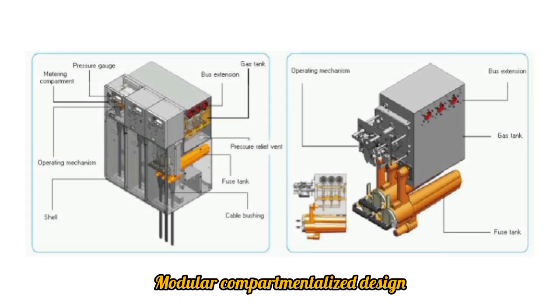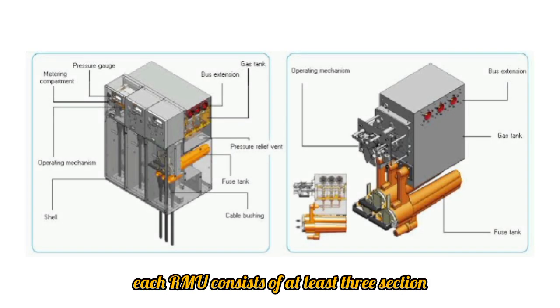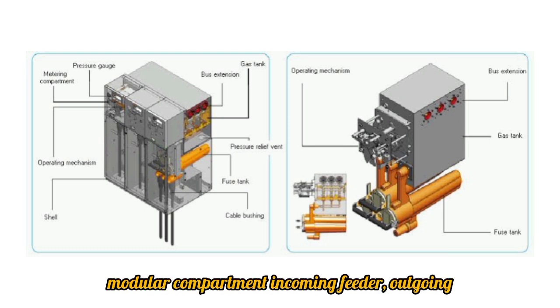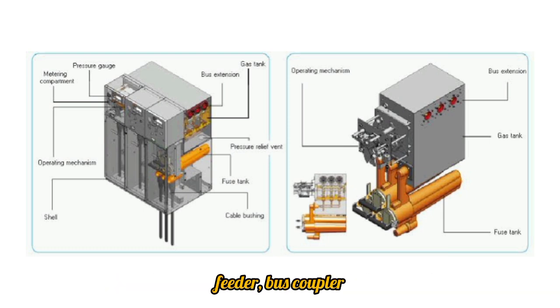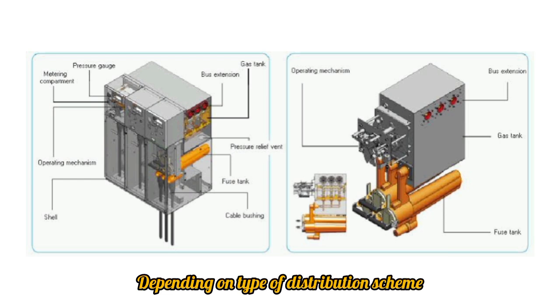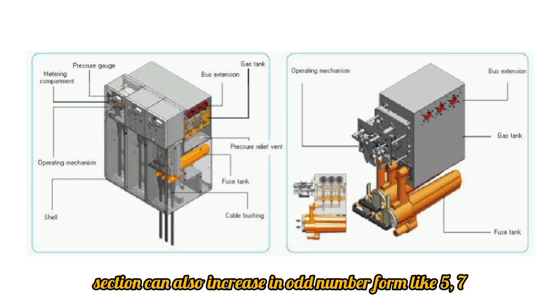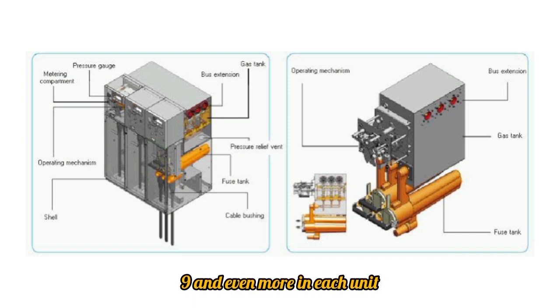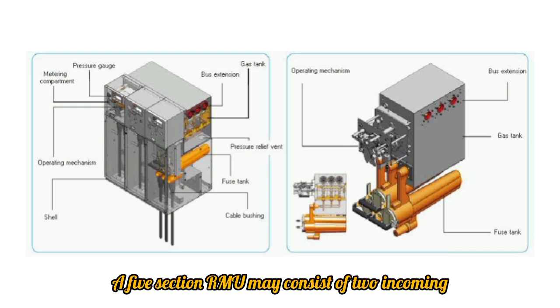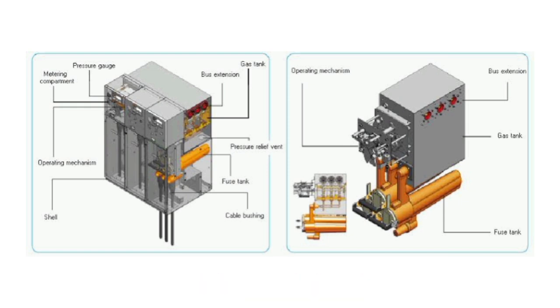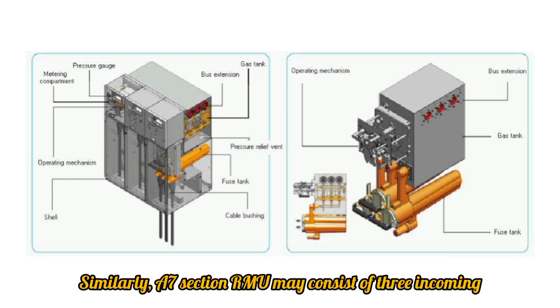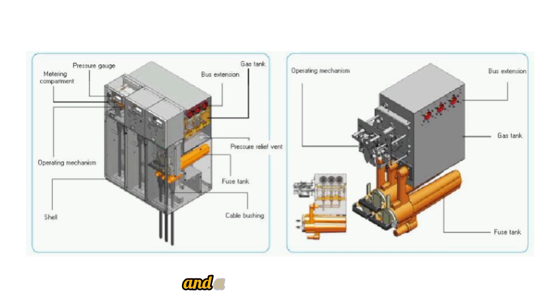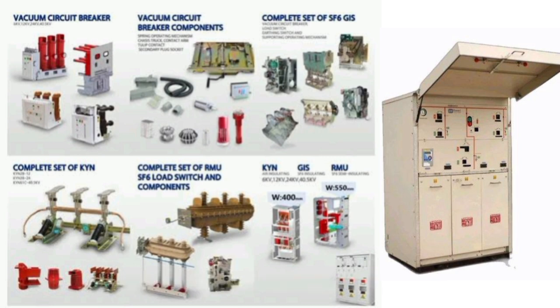Modular compartmentalized design. Each RMU consists of at least a 3-section modular compartment: incoming feeder, outgoing feeder, bus coupler. Depending on type of distribution scheme, sections can also increase in odd numbers like 5, 7, 9 and even more in each unit. A 5-section RMU may consist of 2 incoming and outgoing feeders each and a bus coupler. Similarly, a 7-section RMU may consist of 3 incoming and outgoing feeders each and a bus coupler and so on. Components. Following are the main components used in ring main unit.